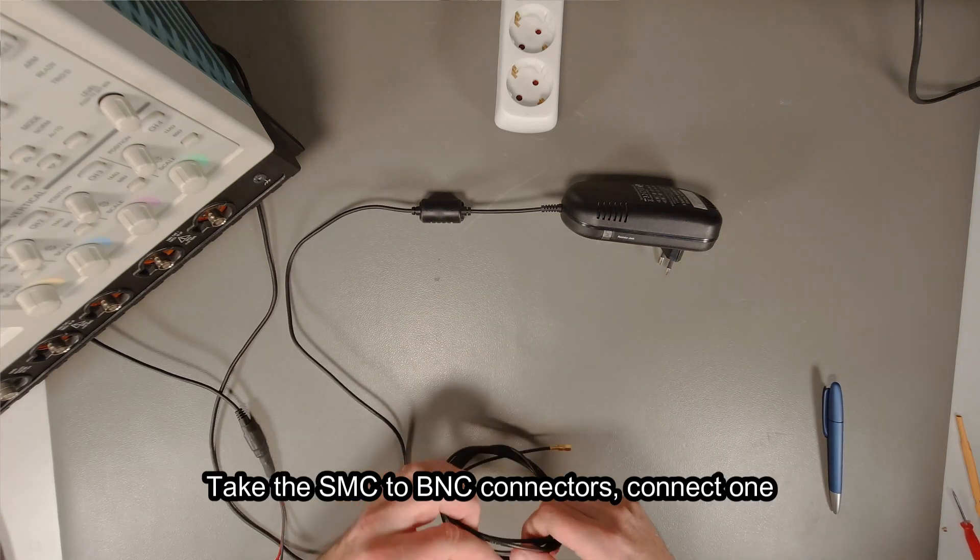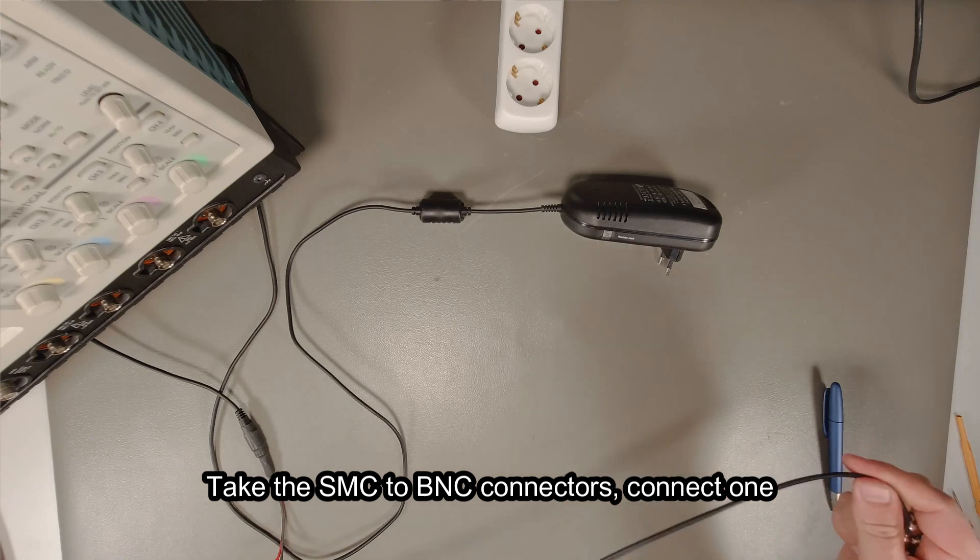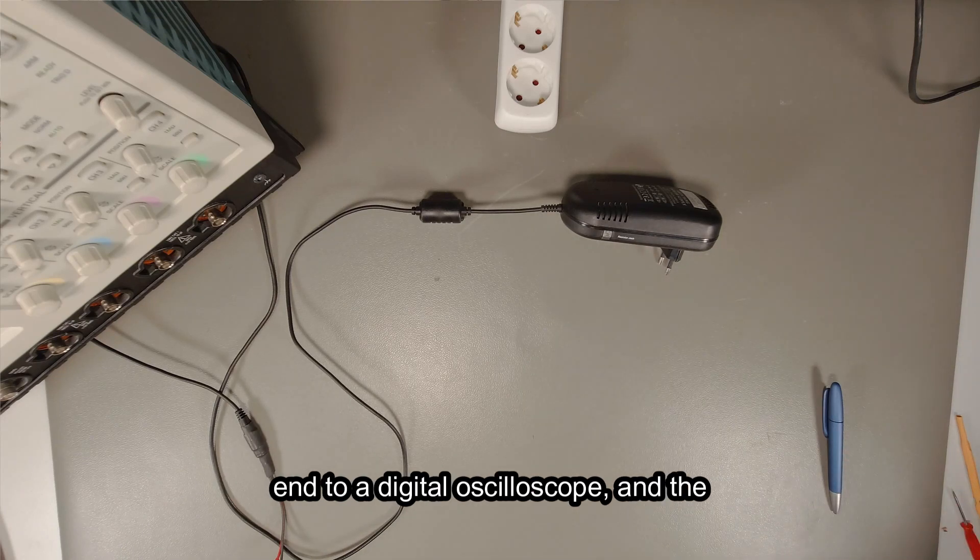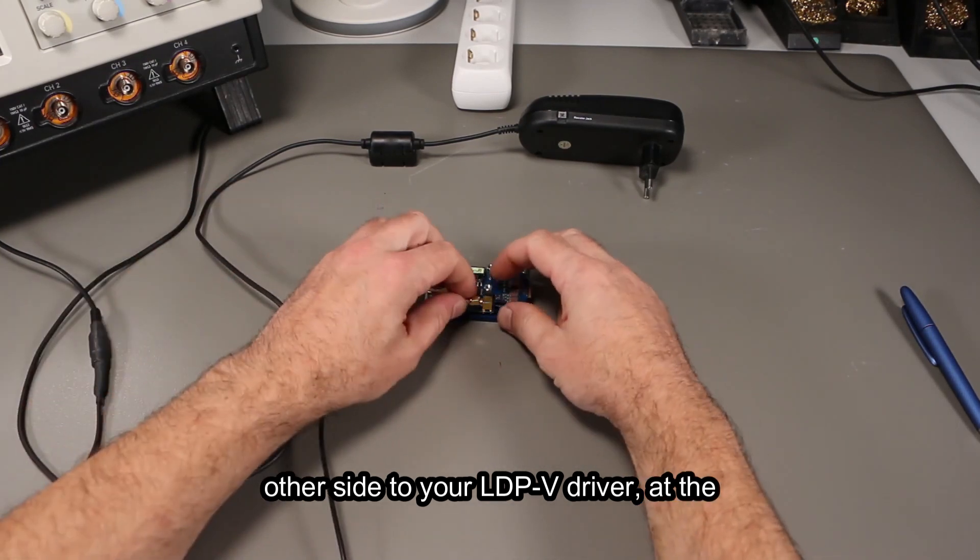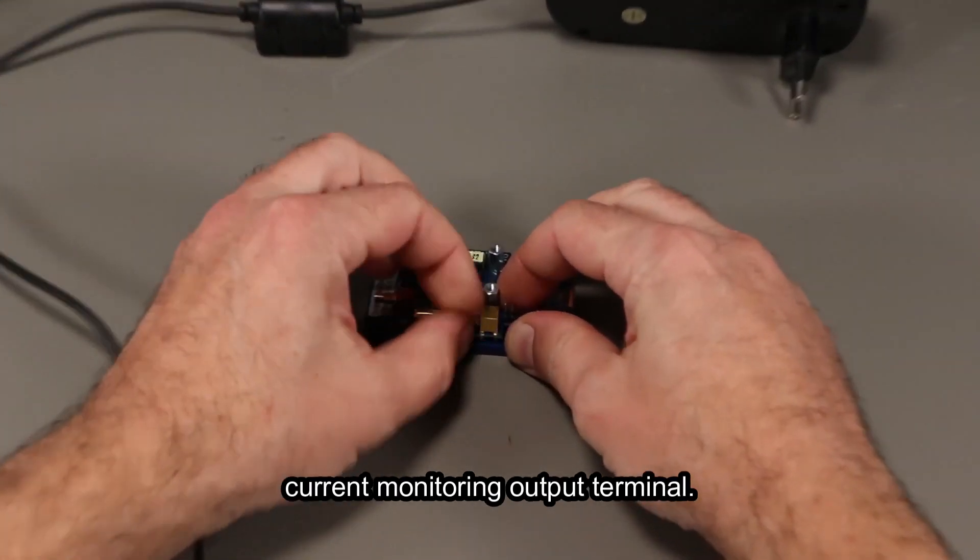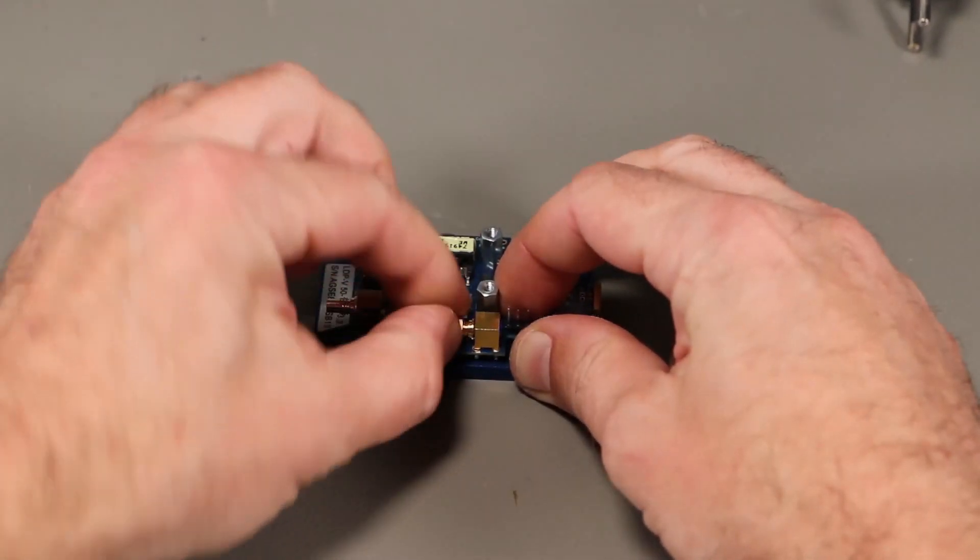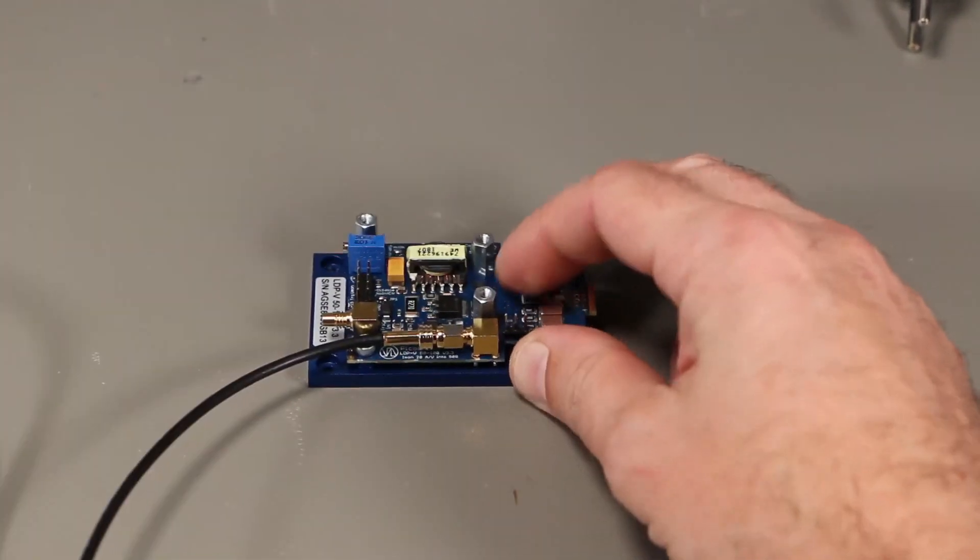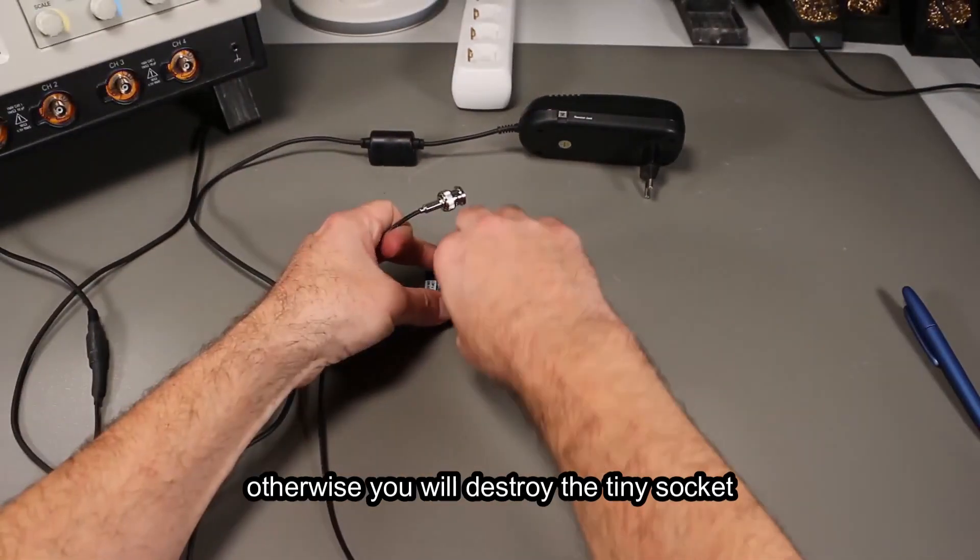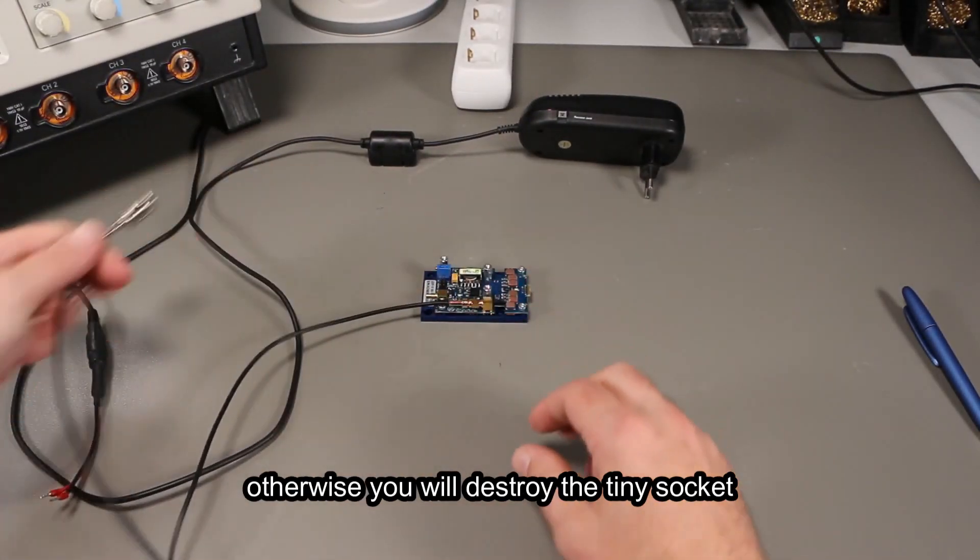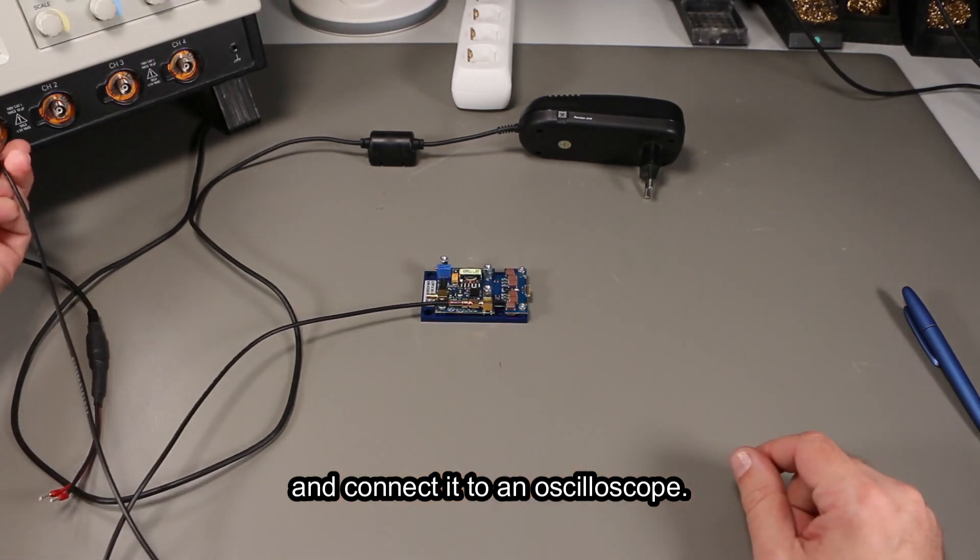Take the SMC to BNC connectors, connect one end to a digital oscilloscope and the other side to your LDPV driver at the current monitoring output terminal. Just tighten it a bit, not too tight, otherwise you will destroy the tiny socket.